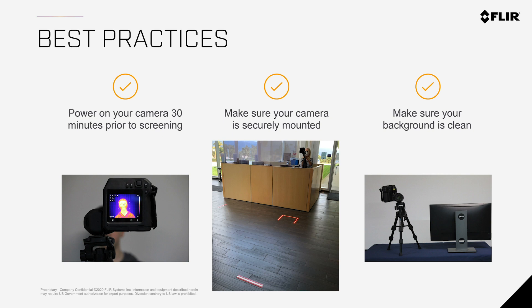First, make sure you power up your camera at least 30 minutes before you start screening. This will ensure the camera gets up to operating temperature and adjusts to the environment.